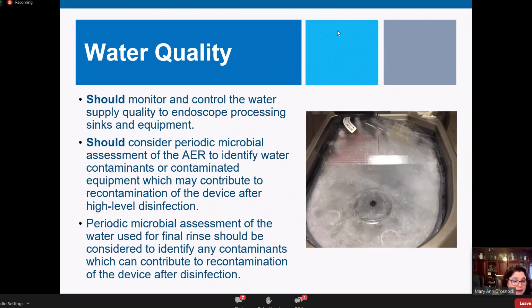This has been done elsewhere in the world for a long time, where they monthly test their final rinse water to demonstrate they don't have a biofilm or contamination issue. We don't have a defined timeline or frequency for that, but we do recommend periodically testing that final rinse water.